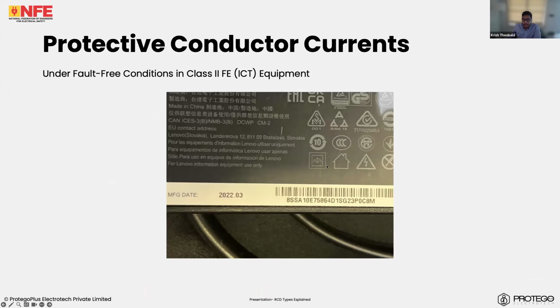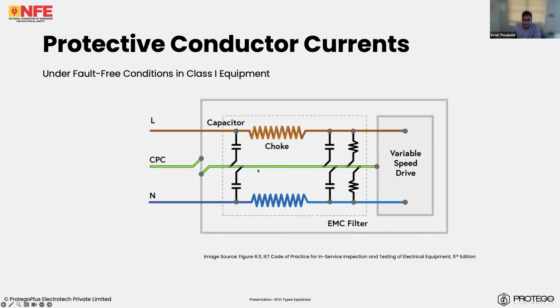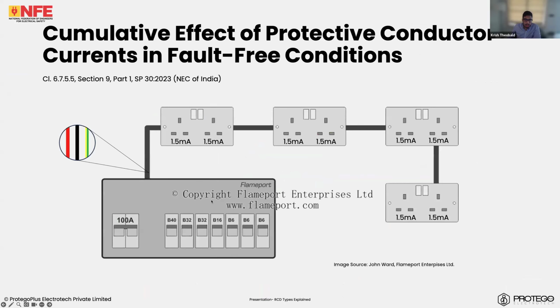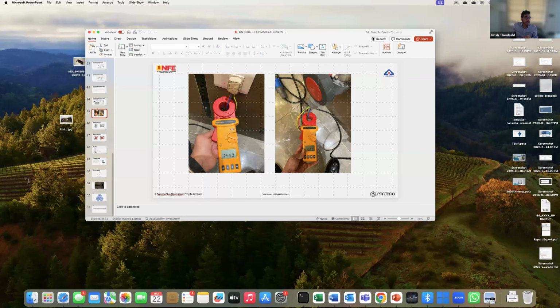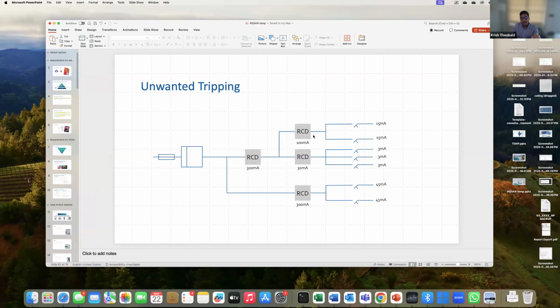What happens is when you have equipment, they have these filtering capacitors like Gerard showed us. And this causes some amount of current to flow through the earth conductor. If you take a thumb rule of 1.5 milliamps per socket, the standard says you cannot load an RCD to more than 0.3 times I delta n. So 0.3 times 30 is 9 milliamps. So 9 milliamps is the maximum threshold. Now 9 milliamps divided by 1.5 milliamps gives us 6 sockets. Any more than 6 sockets, you will have nuisance tripping. The idea is very simple. We do not want to exceed this value. That is why you need to select RCDs only where required. And if it is required for fault protection, then proper sectionalizing, like the diagram that Gerard showed us, is required. Otherwise, you will have nuisance tripping.